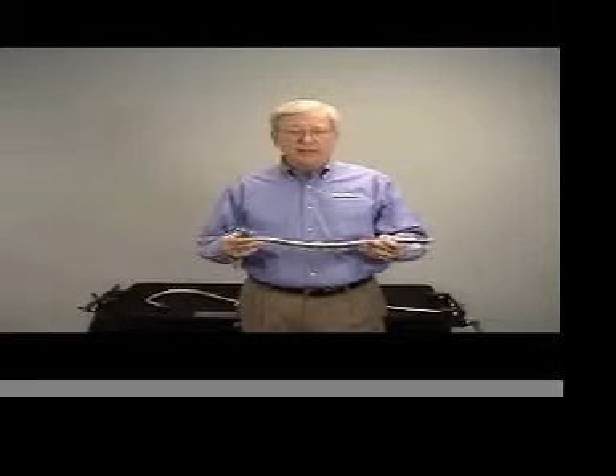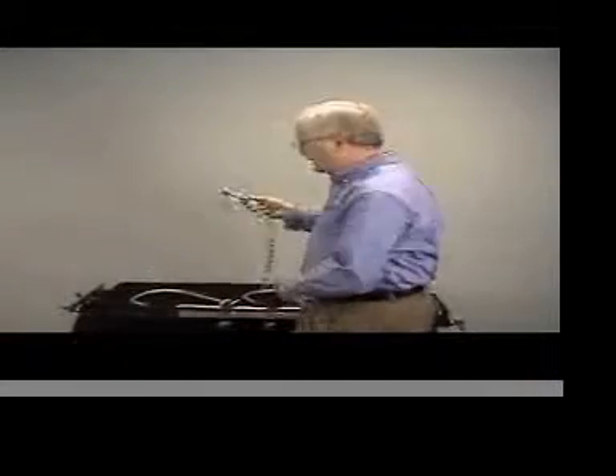Now, this arm has been pre-tensioned. If you notice, there's no opening in any of the knuckles, there's no slack. As I rub my fingers up and down, I don't hear any noise whatsoever. This arm has not been pre-tensioned. You can see as I rub my fingers up and down, you can hear the sound the ball and socket joints make falling into each other. You can actually see the cable at least one point in the arm. So this device needs to be pre-tensioned.